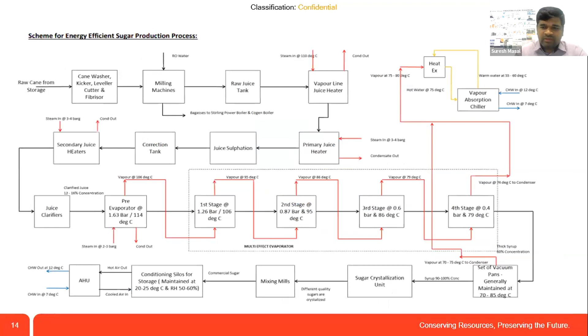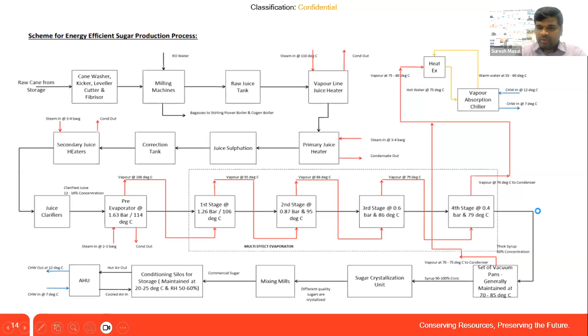In the sugar industry also, there is heat generated, vapor at 70 to 75 degrees. Normally that vapor is given to the condenser, and with the help of cooling water, the vapor gets condensed. Instead, we can take that vapor to a heat exchanger and generate hot water. That hot water we can give to the absorption chiller, and the output from the chiller can be used for cooling and heating applications.